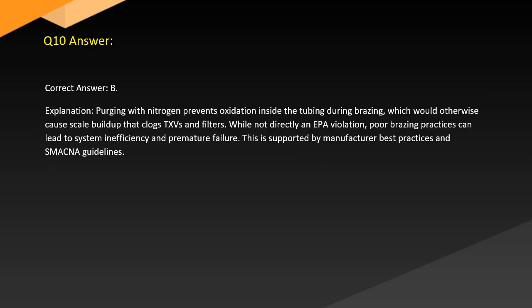Answer. Correct answer: B. Explanation. Purging with nitrogen prevents oxidation inside the tubing during brazing, which would otherwise cause scale buildup that clogs TXVs and filters. While not directly an EPA violation, poor brazing practices can lead to system inefficiency and premature failure. This is supported by manufacturer best practices and SMACNA guidelines.